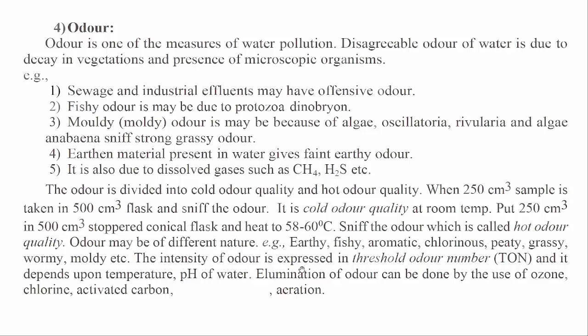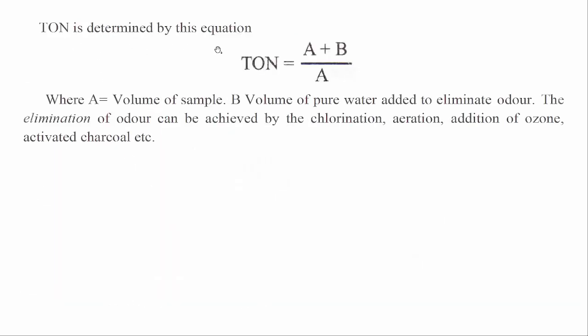The intensity of odor is expressed in threshold odor number (TON), and it depends upon temperature and pH of water. Elimination of odor can be done by the use of ozone, chlorine, activated carbon, or aeration. TON is determined by the equation: Threshold Odor Number = (A + B) / A, where A equals the volume of sample, and B equals the volume of pure water added to eliminate odor. The elimination of odor can be achieved by chlorination, aeration, addition of ozone, or activated charcoal.